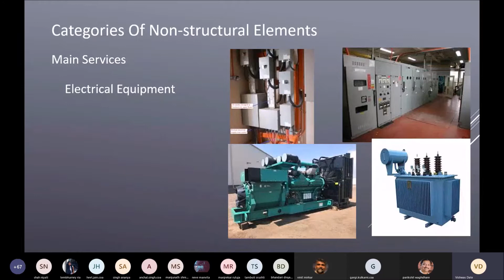So you need to ensure that your generators, your transformers, your electrical panel rooms are safe. Generally panels tend to be very tall, sometimes as tall as 3.5 meters, or it may be as simple as an electrical riser room where your risers are routed. Those need to be very well structured. You have to design them and support them adequately. If particular equipment requires isolation at the base, then it needs to be done properly and maintained properly. Those are the things that matter to you, right?